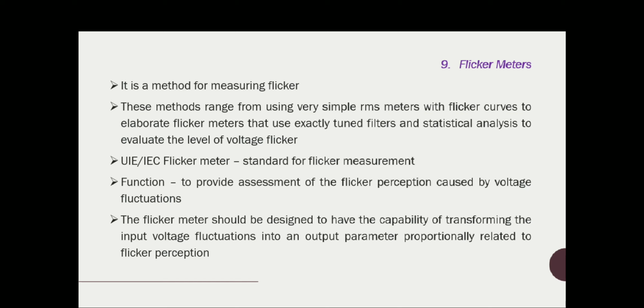You can see that because of the complexity of quantifying flicker levels that are based upon human perception, the most comprehensive approach to measuring flicker is to use a flicker meter. So a flicker meter is essentially a device that demodulates the flicker signal, weights it according to the established flicker curves, and performs statistical analysis on the processed data.